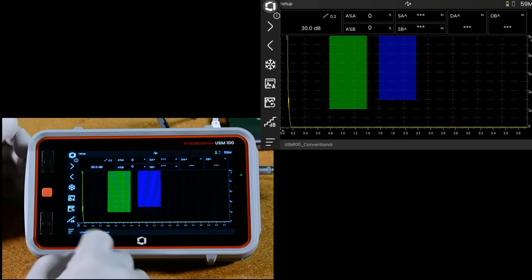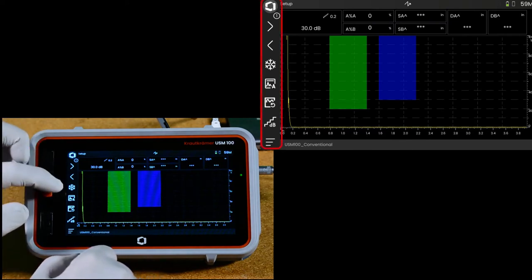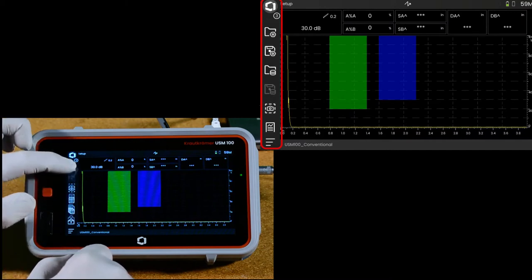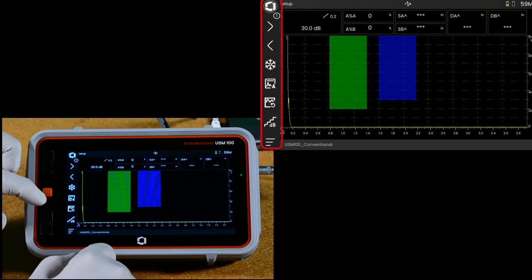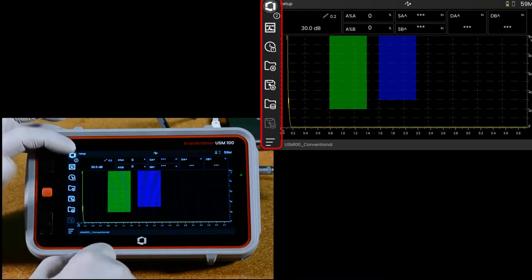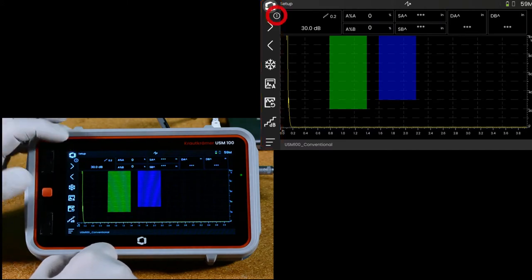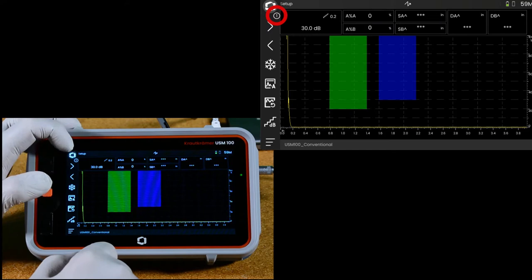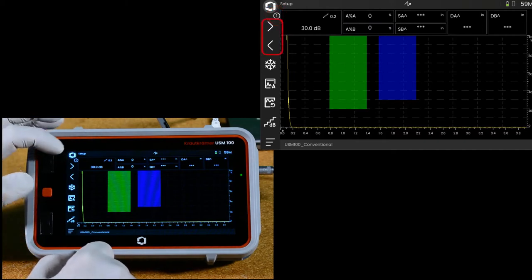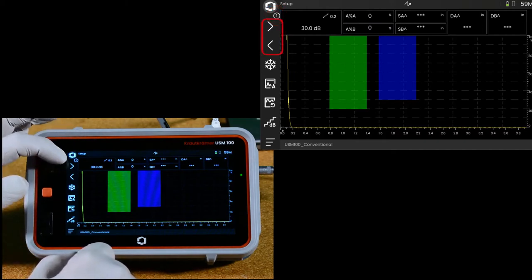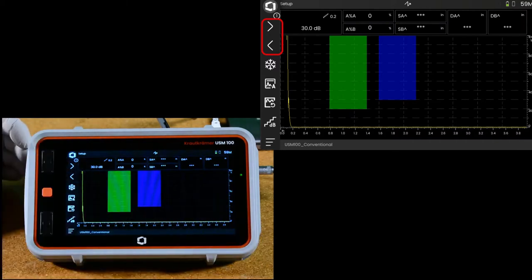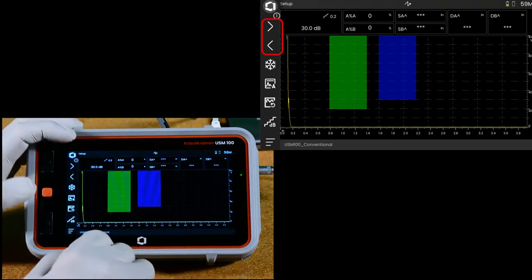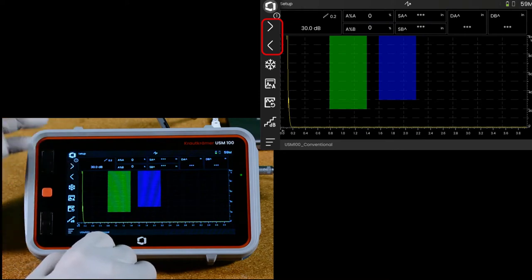Now we can take a look at some of the special features on the USM100. You'll notice the command bar, now that we're in the app, has quite a few more icons to it. We can scroll up and down through the command bar, or we can hit the Waygate button and go page by page through the command bar. There's a little number in a circle right beside the Waygate icon that tells you which page of the command bar you happen to be on. Some of the key features of the command bar, the right arrow and left arrow are panel advance and panel back. So each app has multiple panels. You can move through the panels by hitting the forward and back buttons.